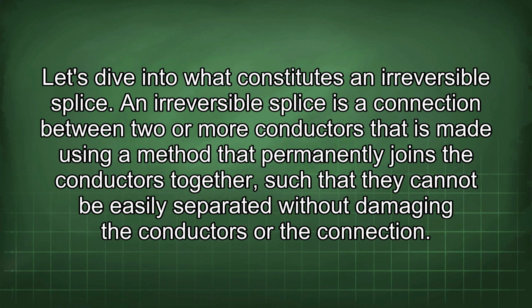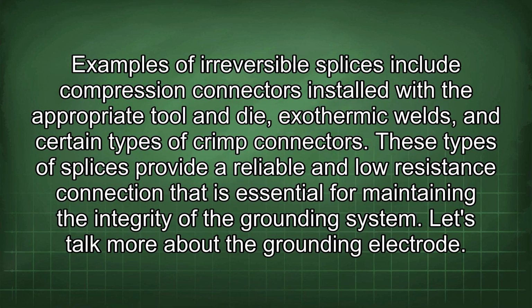Let's dive into what constitutes an irreversible splice. An irreversible splice is a connection between two or more conductors that is made using a method that permanently joins the conductors together such that they cannot be easily separated without damaging the conductors or the connection. Examples of irreversible splices include compression connectors installed with the appropriate tool and die, exothermic welds, and certain types of crimp connectors. These types of splices provide a reliable and low-resistance connection that is essential for maintaining the integrity of the grounding system. Let's talk more about the grounding electrode.